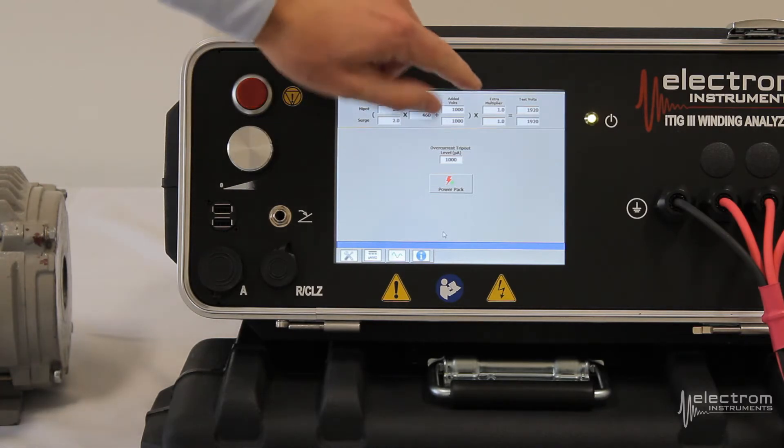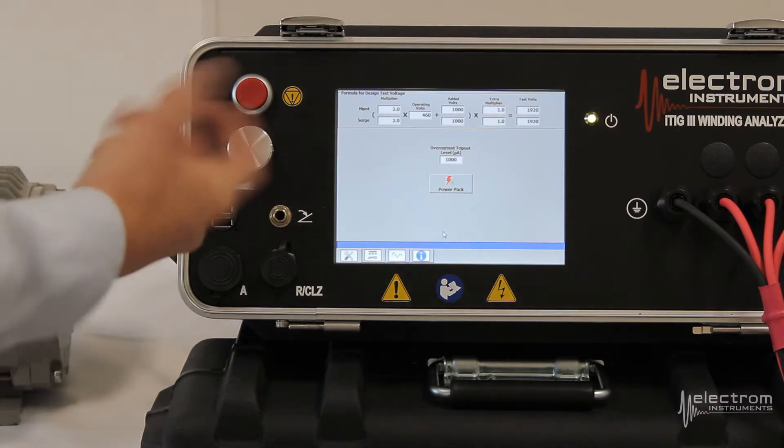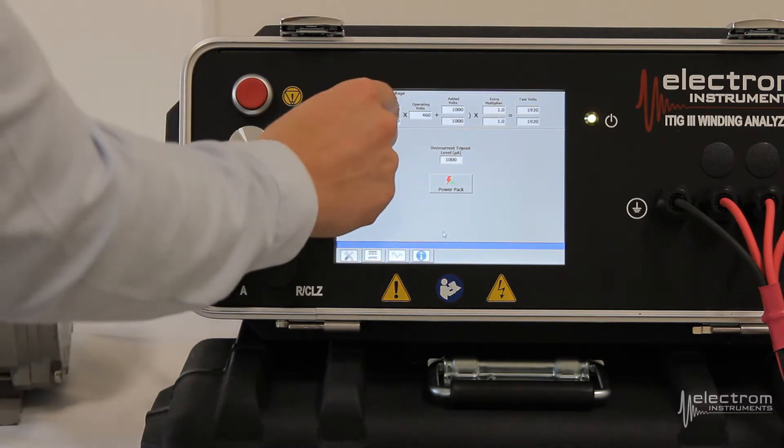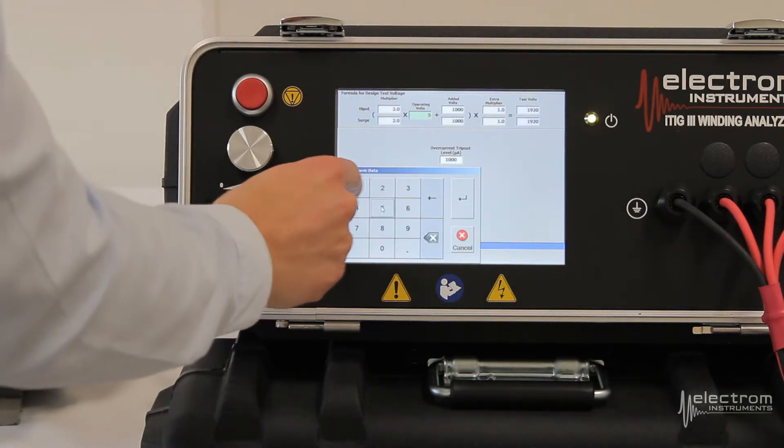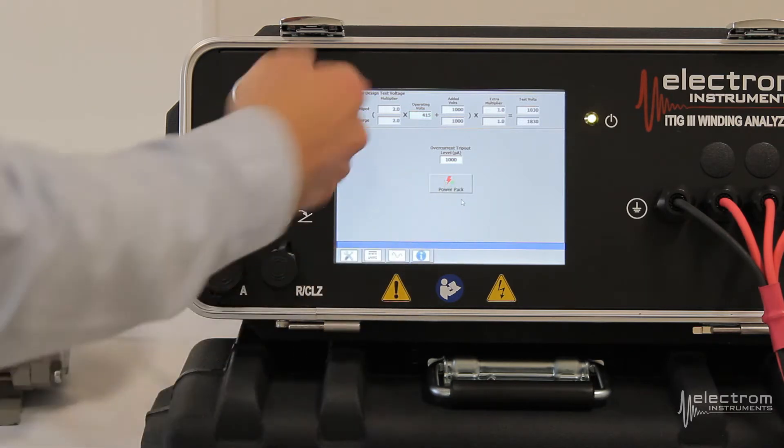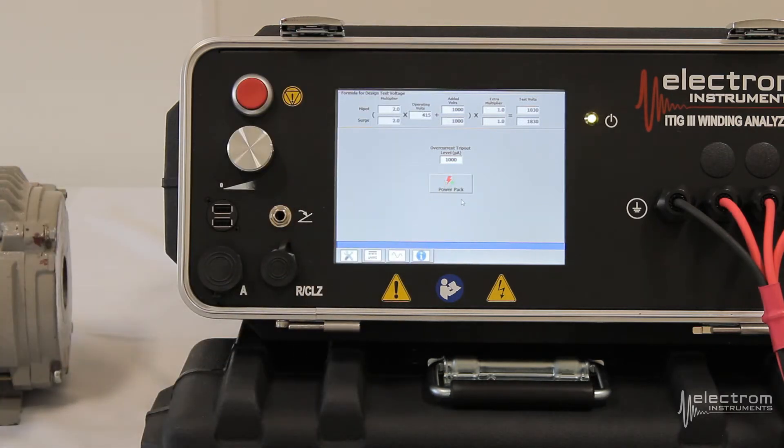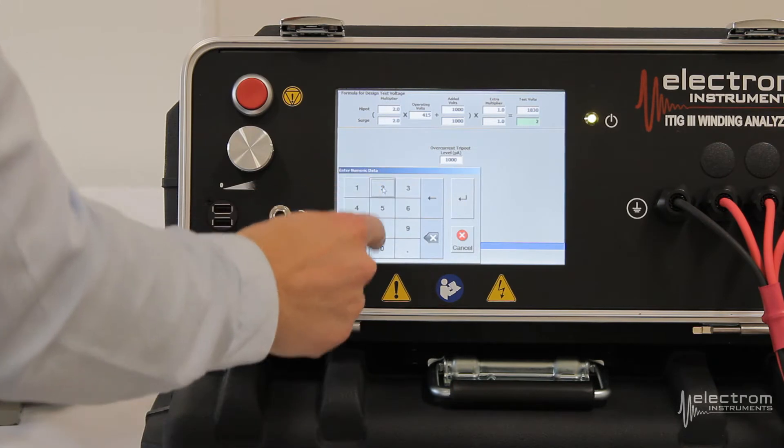There's an extra multiplier here at the end of 1. If you want to change any of the fields you can do so, operating voltage being an obvious one. So let's say this was a 415 volt instead of 460. You would enter in 415, hit enter and it will calculate your new test voltages based on the formula. If you just want to change the test voltage itself you can do so as well.